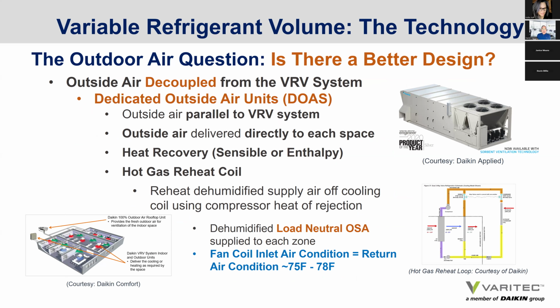So looking at a decoupled outside air approach to VRV, the outside air is parallel to the VRV system. Outside air is delivered directly to each zone. Heat recovery is used in the DOAS unit for free pre-cooling of outside air, so coils are not seeing a mixed air condition of the mid to upper 80s. We have hot gas reheat coil technology with DX DOAS technology, so we can provide free reheat to the supply air properly conditioned at the cooling coil, by using the heat of rejection from compressors to post-heat the air as it comes off the coil.